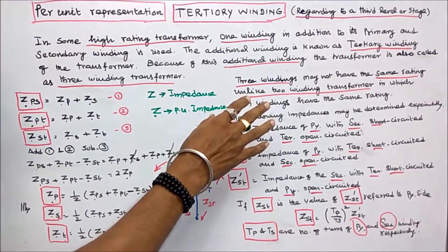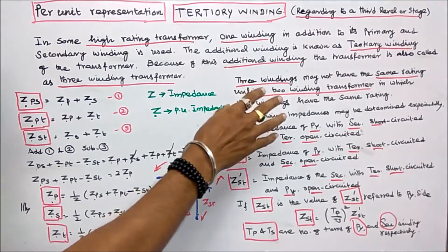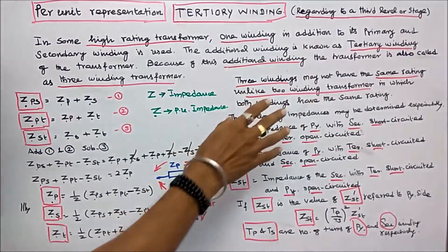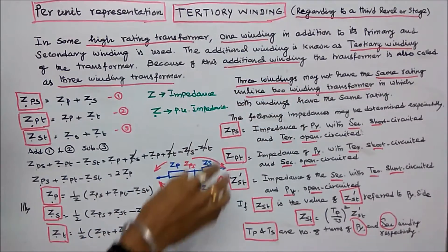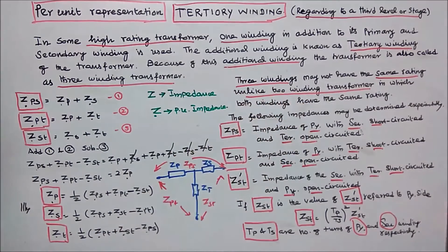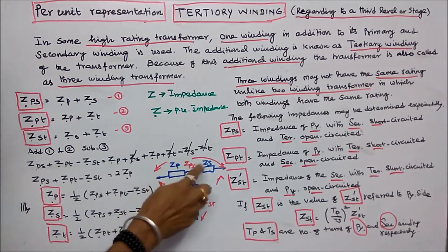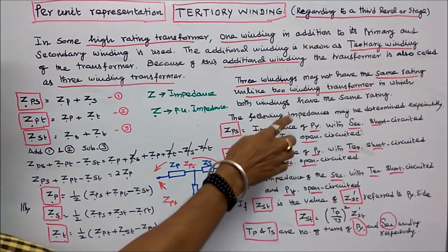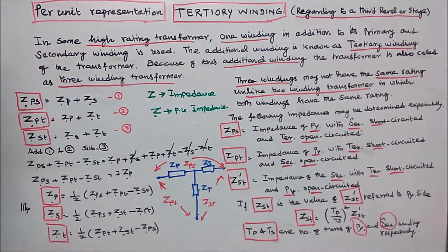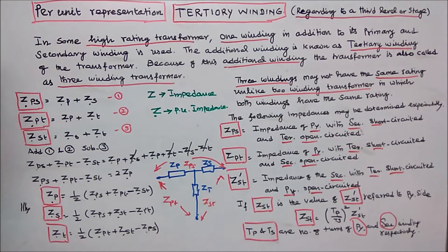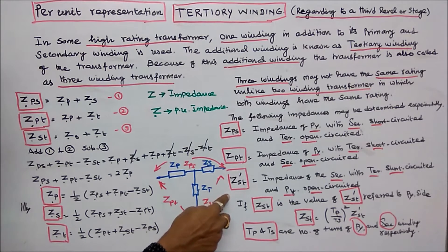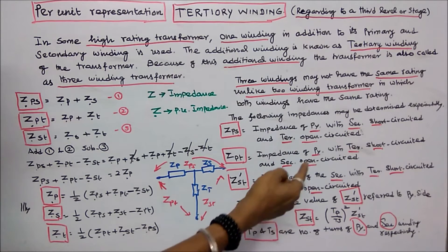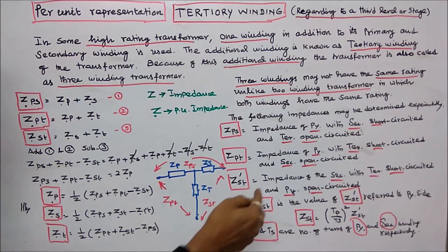Three windings may not have the same rating, unlike a two winding transformer in which both windings have the same rating. The following impedances may be determined experimentally: Zps is equal to impedance of primary with secondary short circuit and tertiary open circuit. Zpt is the impedance of primary with tertiary short circuit and secondary open circuit. Zst dash is equal to impedance of secondary with tertiary short circuit and primary open circuit.